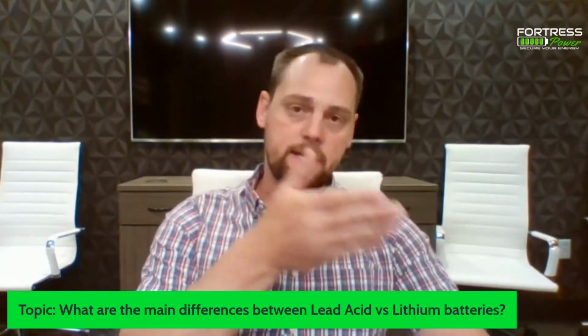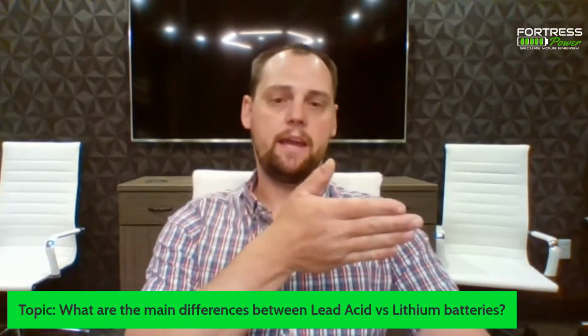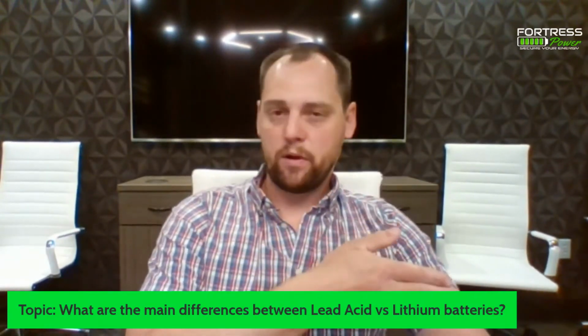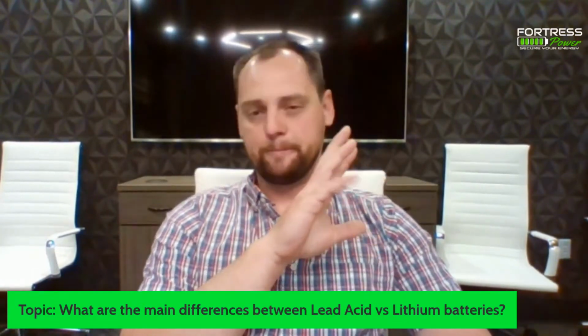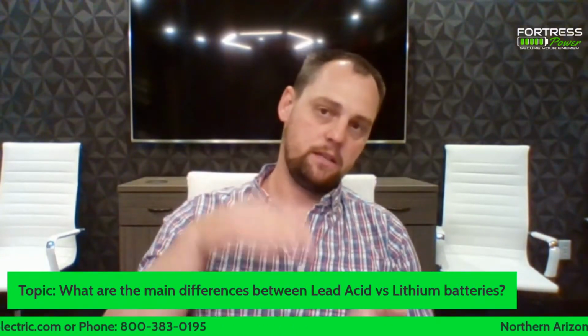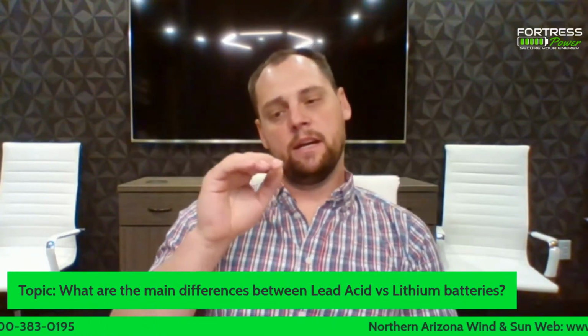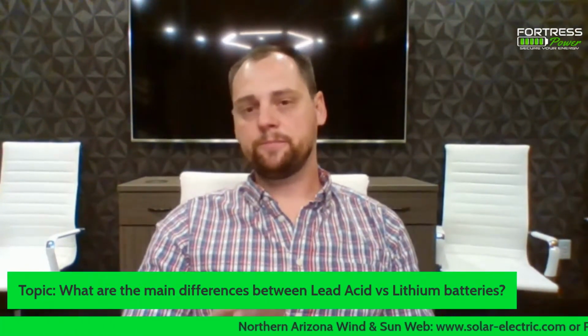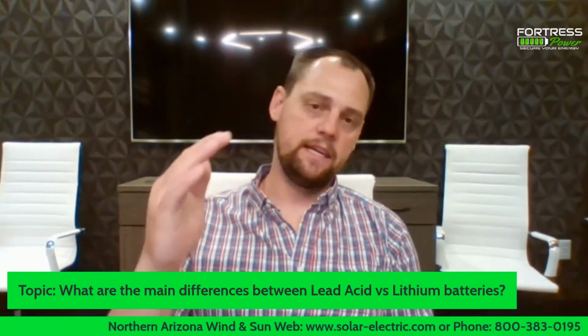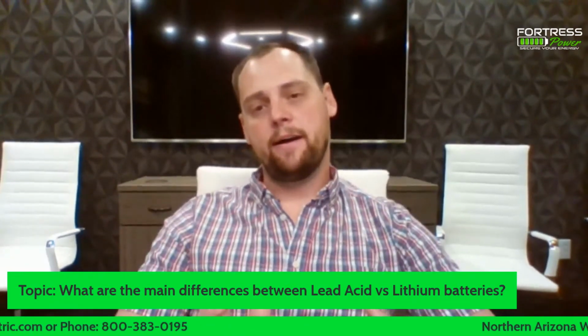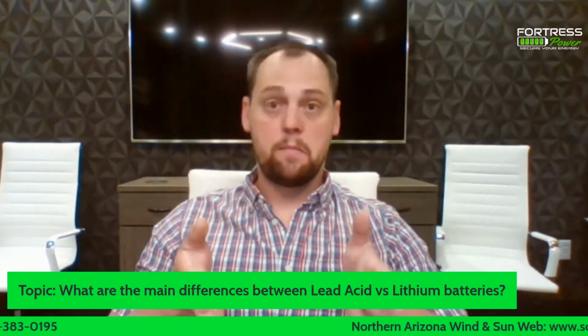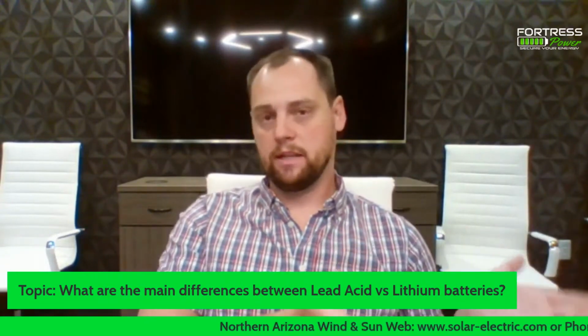For example, they off-gas hydrogen, they're caustic, and they suffer from partial state of charge. They cannot be expanded, and that same goes for AGM in the sense that they can't be expanded either. AGM is a little more expensive, but it's a maintenance-free solution. Depending on the chemistry, they may or may not suffer significantly from partial state of charge, but at least they're a maintenance-free variant of a flooded lead acid battery.